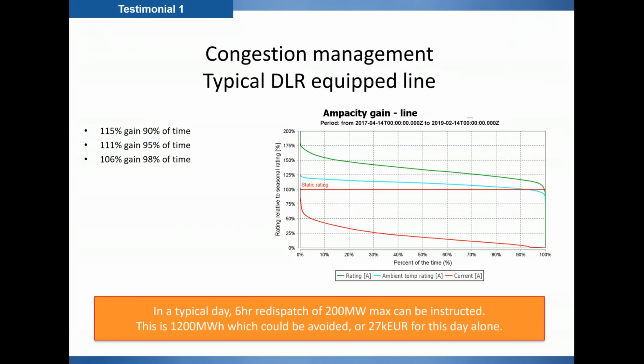This is a fairly typical example of the distribution of DLR that you would see over a year. In this example, that's the green curve here. 50% of the time, so the median point is about 30 or 35% of capacity increase. So that's the median. But still, if you take the extreme of the curve, you would still gain approximately 15%, 90% of the time, and still 6%, 98% of the time.